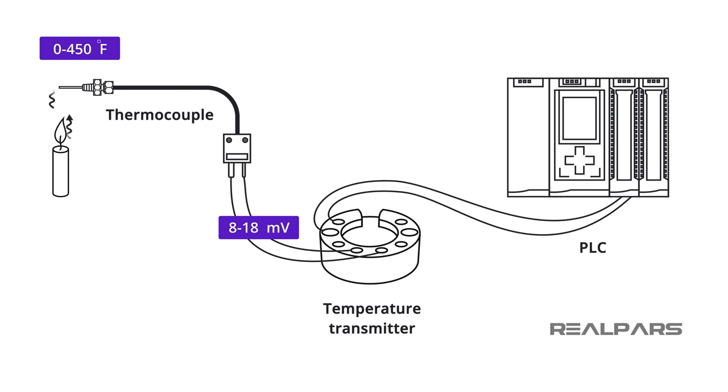In process control, we condition that 8 millivolts to 18 millivolts thermocouple voltage and convert it to a 4 milliamps to 20 milliamps industry standard signal that represents our controlled temperature range.